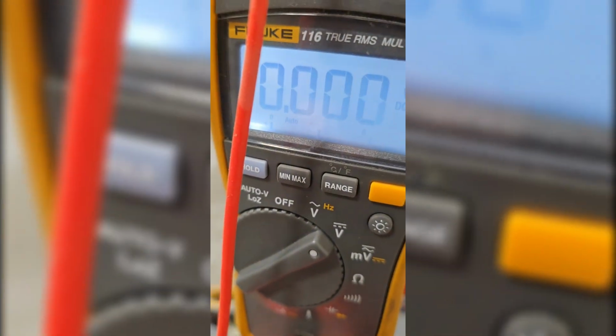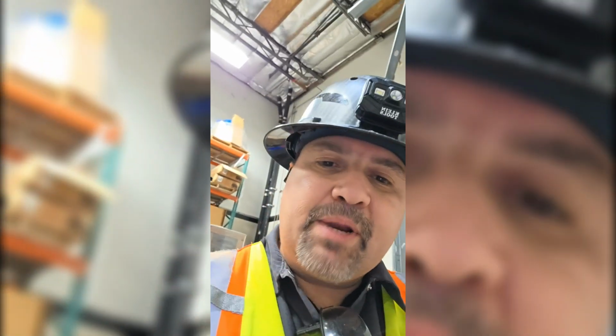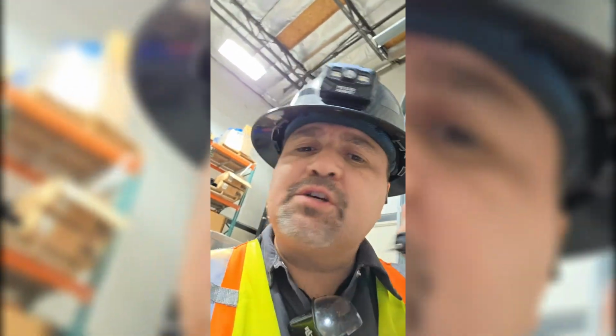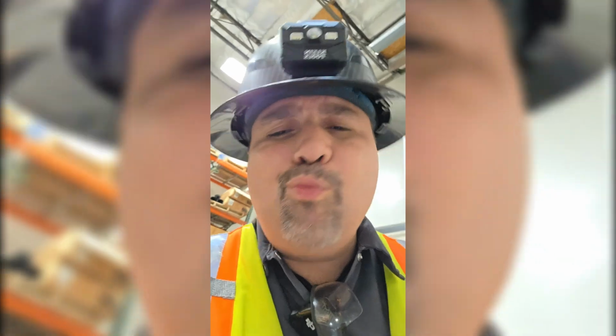So now I got my probe locked into the other side. I got my switch cycled on. Let's hit this ground, see what we got. We got nothing. So right away, when I close my switch, I'm not transferring power from one side to the other. Something internally, the internal contact, is no bueno.